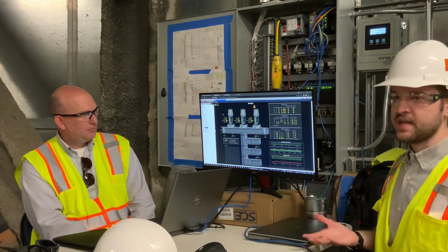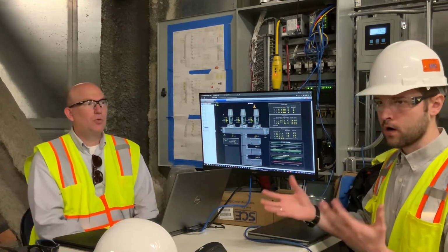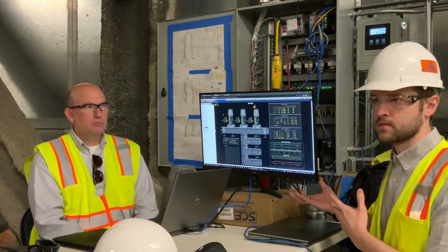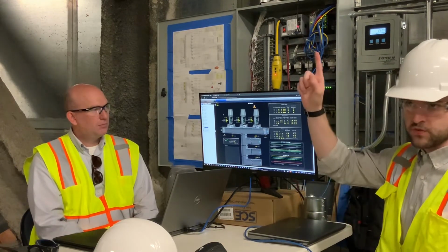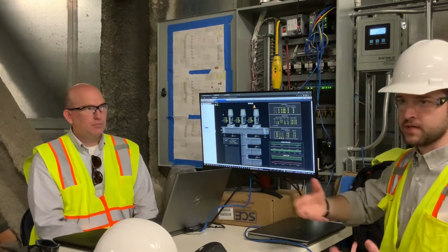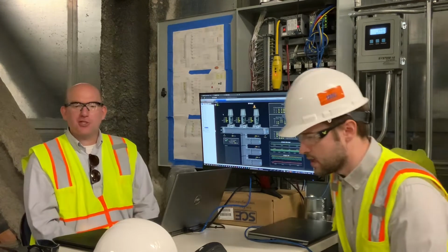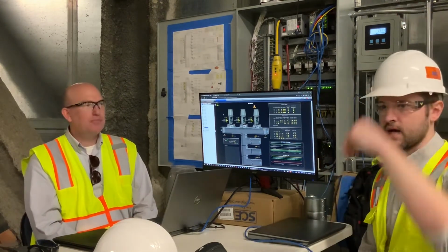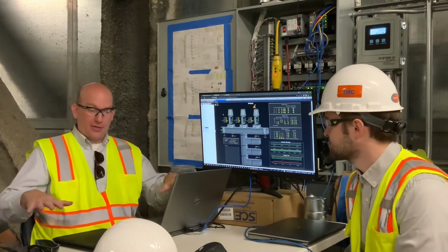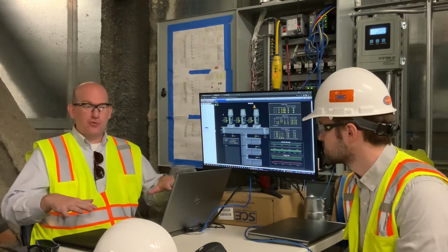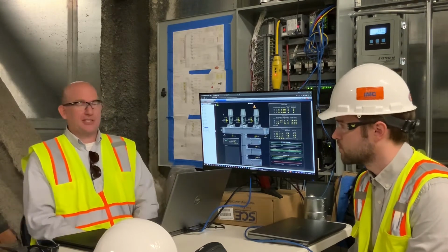If the fan speed is high enough, and I don't know how familiar you guys are with lab exhaust fan control, but the basic premise is that you're blowing air as high as possible to make it safe to evacuate whatever you're pulling out of your lab. Disperse the contaminants as much as possible. So you're trying to get that plume height sufficiently high so that the EPA calls it safe, right? And nothing contaminates the roof, so if somebody has to go out there and work, they're not going to breathe in a bunch of nasty stuff.